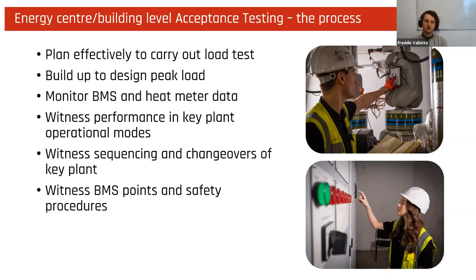In particular, it will focus on key plant operation modes, i.e. additional boilers or pumps coming on or offline, changeover of heat generation equipment once the thermal store is depleted, for example. This particular focus on sequencing and changeovers ensures that heat delivery is not compromised in these periods of changing load, return temperatures actually remain low and as per design, and your pump differential pressure is maintained across the network. Heat meter data becomes incredibly useful at this stage as flow and demand can be monitored at all points in the system alongside your temperature and pressure data obtained from your BMS.